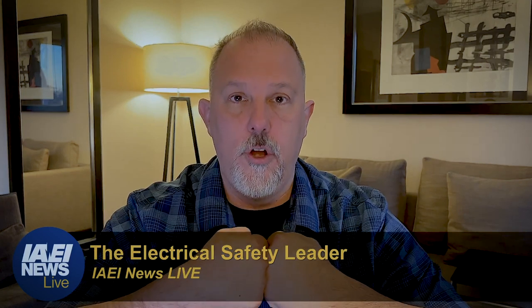I don't like the term insulated case circuit breaker because it's a marketing term. It's not defined in the standards. Back in the day, and I'm not sure what year it occurred, but it was in a land far, far away, in a distant time, all that jazz. What the industry needed was, you have the power circuit breaker, which is the big hunk of metal and Swiss watch that goes into switchgear. And then you have the molded case circuit breaker that goes into panelboards. They needed this interim stop in between a molded case circuit breaker and the big power circuit breakers. They needed a circuit breaker that could hold those contacts closed longer for higher currents.